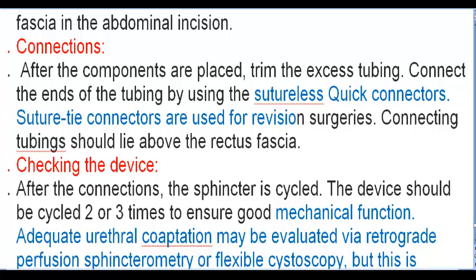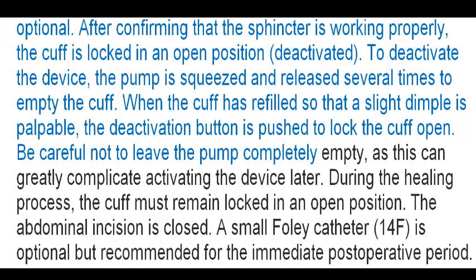Adequate urethral coaptation may be evaluated via retrograde perfusion sphincterometry or flexible cystoscopy, but this is optional. After confirming that the sphincter is working properly, the cuff is locked in an open position, deactivated. To deactivate the device, the pump is squeezed and released several times to empty the cuff. When the cuff has refilled so that a slight dimple is palpable, the deactivation button is pushed to lock the cuff open. Be careful not to leave the pump completely empty, as this can greatly complicate activating the device later.